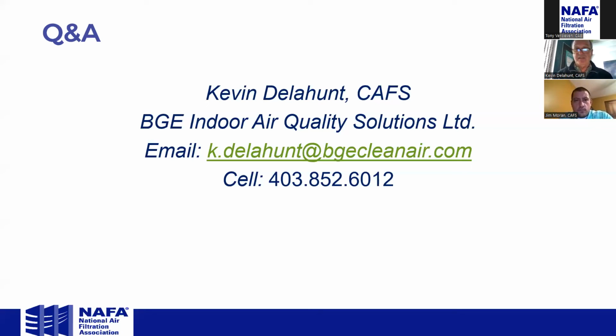So in going from MERV 8 to MERV 13, we need increased filter media, so more square footage of media, either something with additional pleats, or preferably I would like to see just more depth in the filter. So if there was a 2-inch channel, can we change that channel to a 4-inch or 6 or an 8-inch channel? And with that, we would get a lot more opportunities to provide the level of filtration without impacting the volume of air in the space.